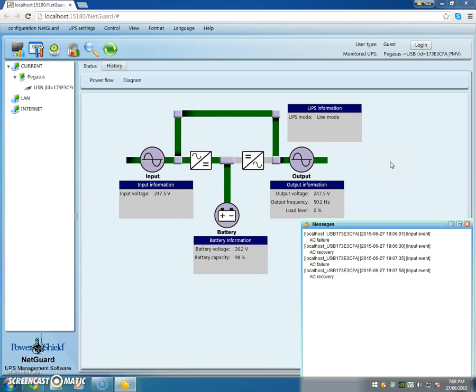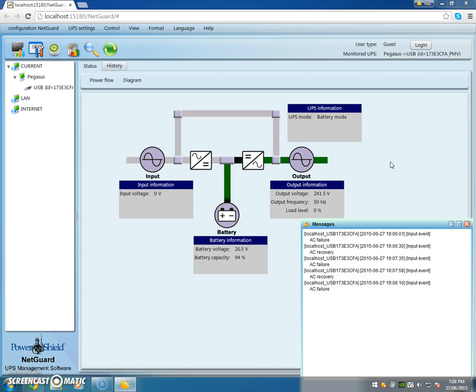And one more time just so that we're very clear on what's happening, I'll pull the plug again. AC failure and you can see this input drop out to zero, power has been fed off the battery through the inverter now to the load.